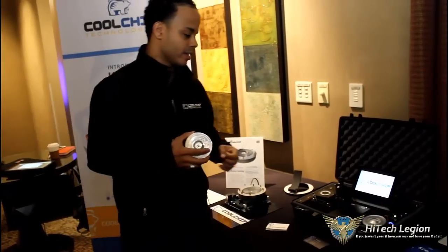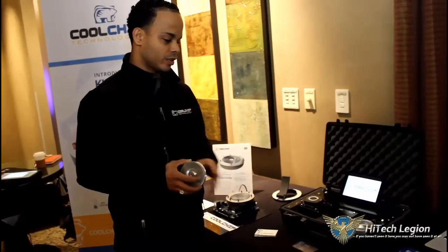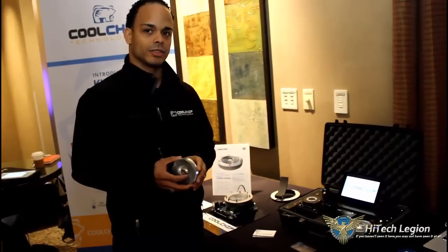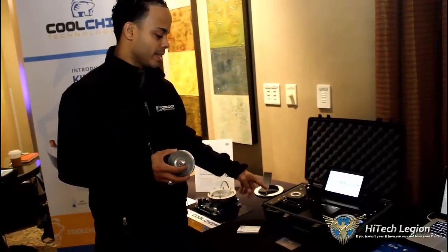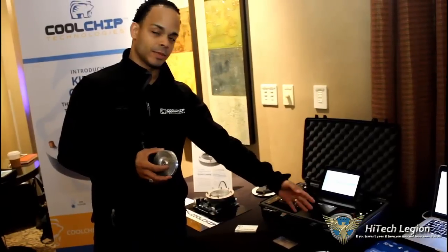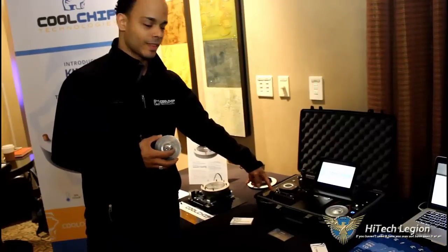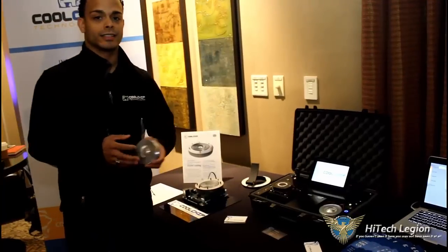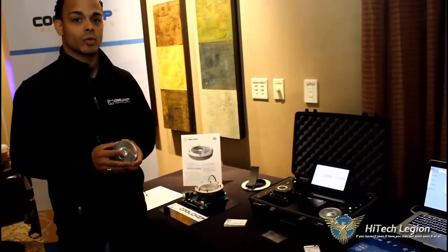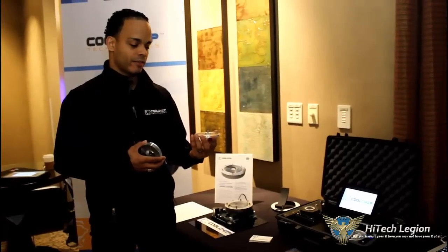We've got an interesting demo here where we fix the size and fix the amount of heat removal. This is a 1U server application, but listen to what happens when we turn on a commercial part. Here I've got our kinetic cooling engine — it's been running the whole time I've been speaking. Here's what happens when I turn on this guy. You can probably pick up some of that audio. It's about a 20 dB delta in sound, or roughly 100 times quieter.